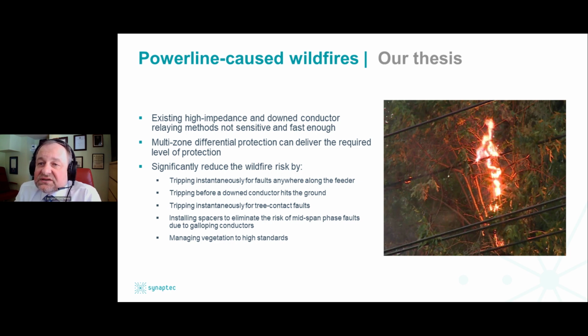So our thesis is that you could significantly reduce the wildfire risk, or reduce it enough, by practicing better protection and by practicing hygiene. So better protection is differential, and you will be able to trip instantaneously for faults anywhere along the feeder, trip before a down conductor hits the ground, or at least have a significant chance of doing that, and also trip instantaneously for tree contact faults or other high impedance faults. Better hygiene means that you keep the feeder in good shape.